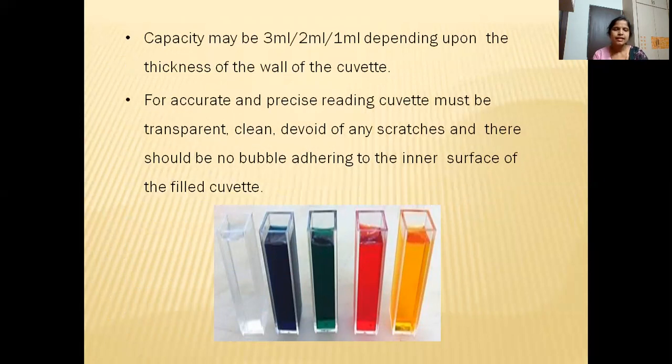And you can see these are the cuvettes which are filled with the solutions, and always you have to see that the solution is filled only up to 3/4 of the cuvette, and you have to hold it with your fingers touching the frosted side, not the clear side. So for accurate and precise reading, the cuvette must be transparent, it should be clean, it should not have any scratches, and there should not be any air bubbles. So when you fill the cuvette with the solution, you have to check that there are no air bubbles in it.